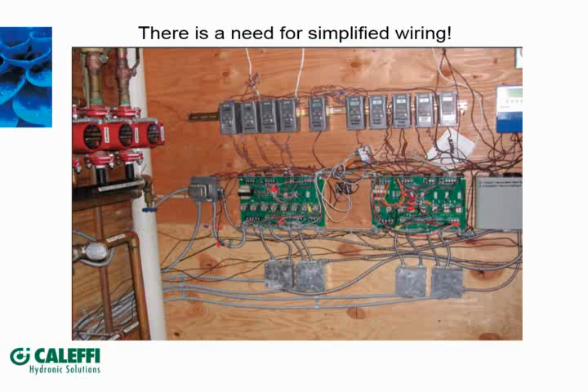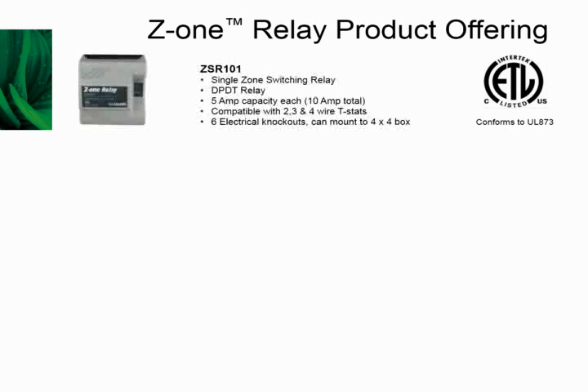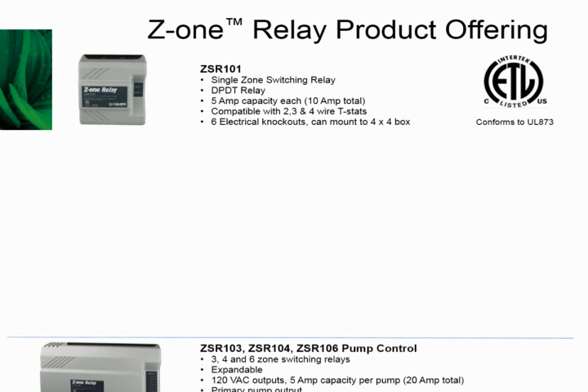The family of products, we basically have 3 different families inside of here. They are all approved by ETL for CUS, and it conforms to the UL 873 standard. So the first one is the simplest one. We call it the ZSR 101. It's a single zone switching relay. It's basically a double pole, double throw relay. Has a 5 amp capacity on each leg, and it's compatible with all 2, 3, and 4 wire thermostats. We'll get into the details of our wiring later. It has 6 electrical knockouts, 3 on the top, 3 on the bottom, and one thing that's kind of neat is that it can mount to a 4x4 electrical box, so you can really get a nice clean looking installation on these.